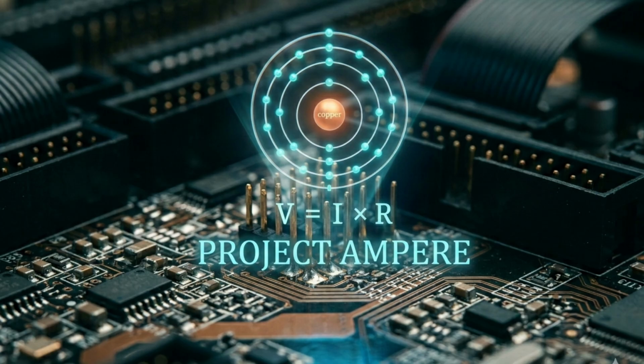Right. If you put a standard fast-acting fuse on that motor circuit, it would blow every single time you tried to start it. It would see 75 amps and instantly say, too much, pop. So you would literally never get the motor running. You'd be grounded. A slow-blow fuse is specifically designed with a heavy thermal mass. It sees that 75 amp spike, and it essentially says, whoa, that is way over the limit, but I am going to wait.